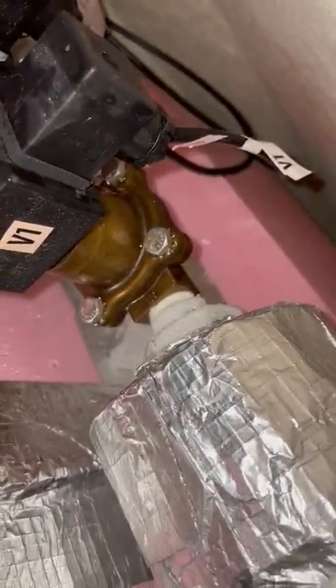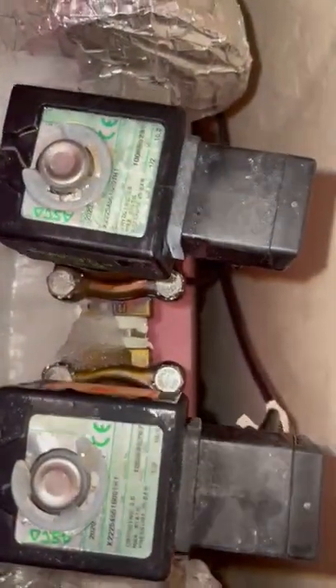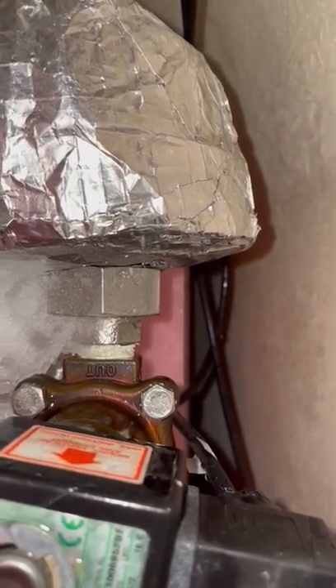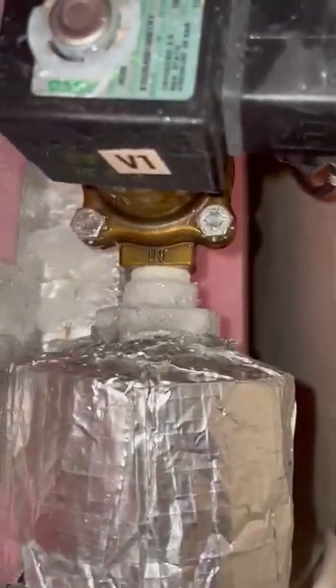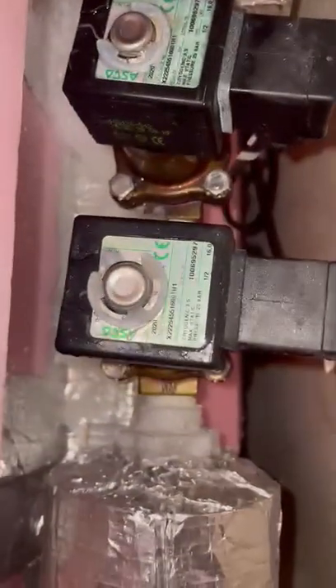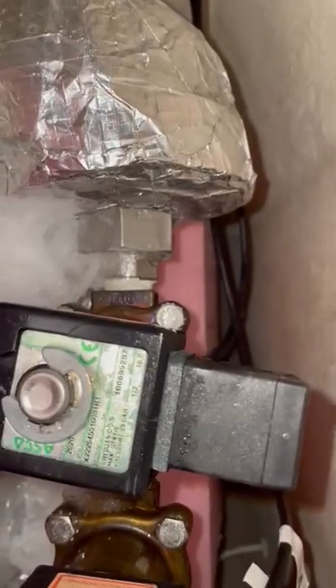We can go here and make sure there's not a leak there. You can also do it from a side angle — just try to focus if you can. If you ever see a steady drip of liquid that is not defrosting ice, then that's likely an issue. Normally this is going to be your best view — right above it, right past the second one — which will tell you if there's a union leak usually. You will want sessions running. If you don't notice a leak without a session running, go ahead and run sessions. If you see the leak, we will also send you a video of what an example looks like — this is what we're wanting to get because it will help us determine what leak you have.